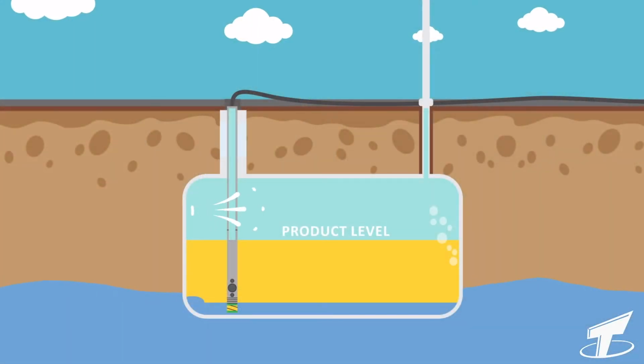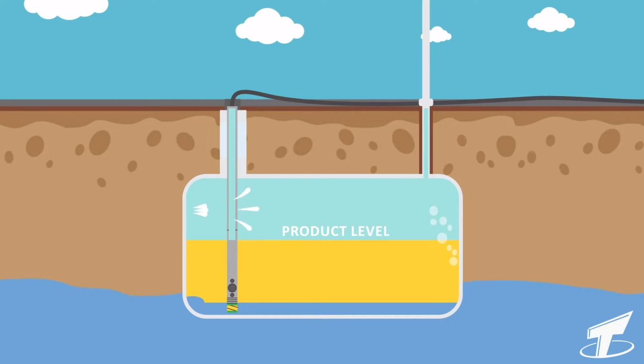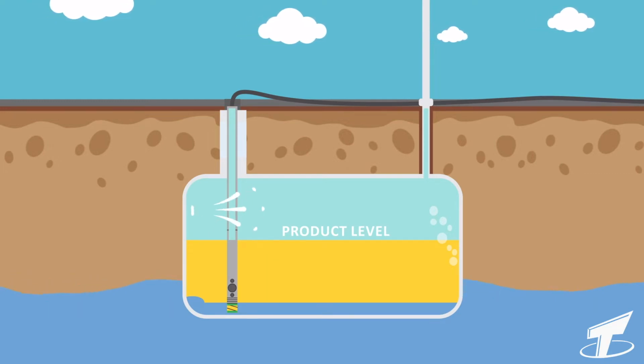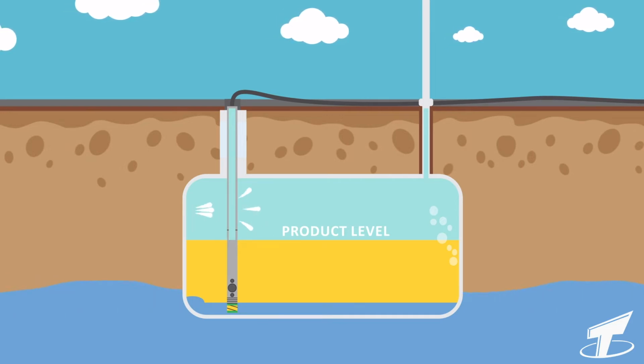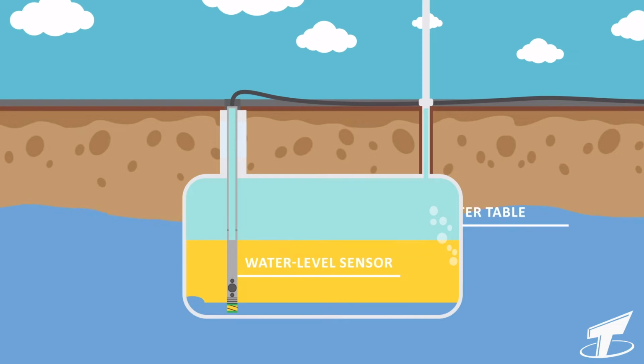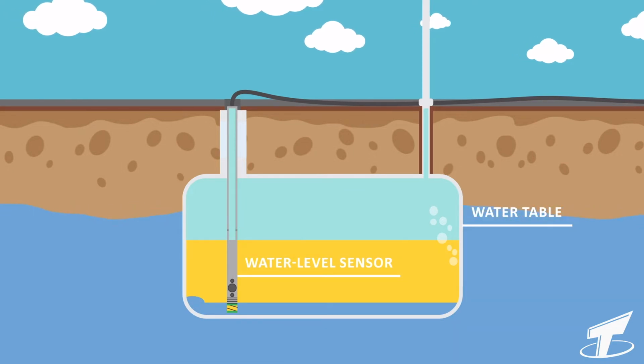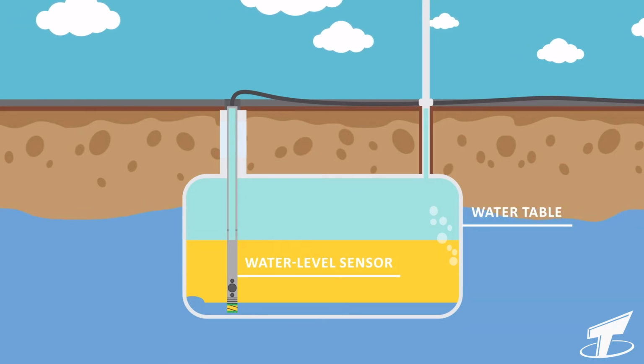A leak above the product level, including in the vent, creates a distinctive hissing sound, a loss of vacuum, and constant cycling by the vacuum pump as it restores the vacuum. This is a positive indication of a leak. VacuTect identifies leaks even in tanks situated in areas with a high water table.